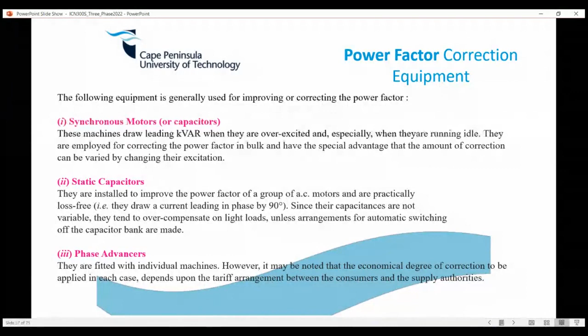You have static capacitors. This is the most old school and the cheapest way as far as I know. Essentially, the power factor is improved by capacitors in parallel with the operating equipment, which is operating at a lagging power factor. We have a capacitor bank, and we hook it up either to the motor or at the supply to improve the power factor, because as we know, capacitors provide a leading power factor or positive reactive power, and that compensates for the negative Q, so to say.